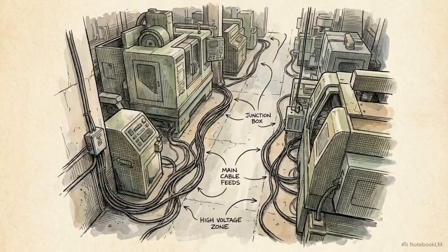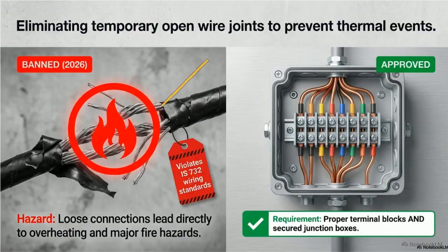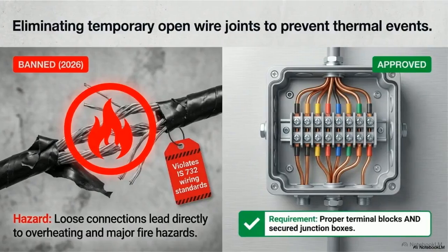Next, we have to address the localized power connections and semi-permanent fixtures scattered across the shop floor. Look left. Twisting wires and wrapping them in tape leaves the connection loose, causing extreme overheating and major fire hazards. Now look right for the required solution. All taped joints must be replaced with proper terminal blocks, completely secured inside closed junction boxes.